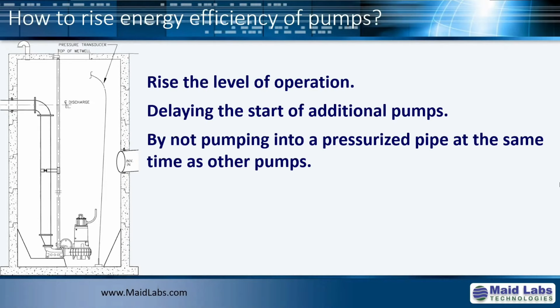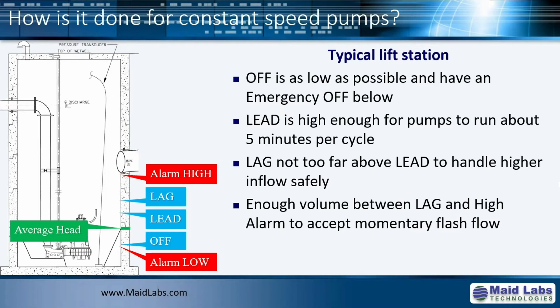so a typical lift station works this way. You have a lead level, a lag level, an off level. Usually they are relatively low in the lift station so that you can accumulate some water above it if you have a peak, and that's how they all work. I mean, 98% of the pump stations are working this way. So if you go to the next, and by the way, this gives you an average head, which is in the middle between the lead level and off level when you have only one pump operating. The idea is to try to increase or to lower that head, okay, as much as possible.